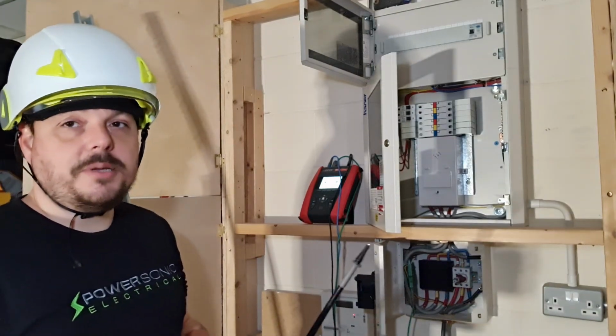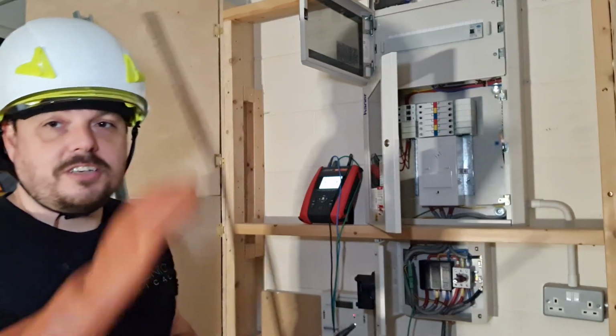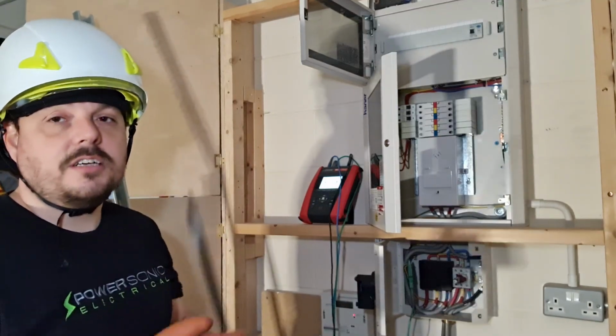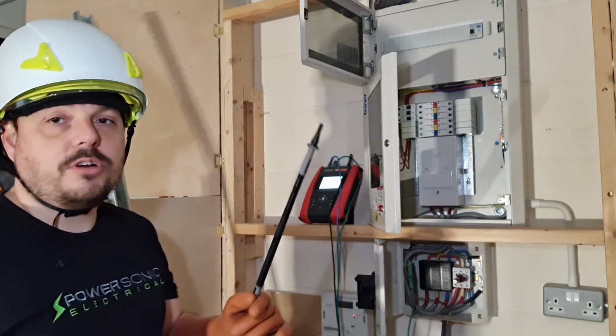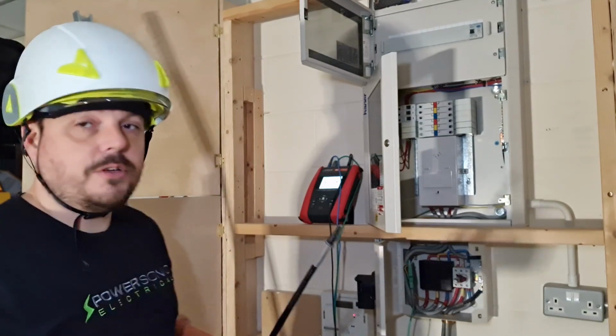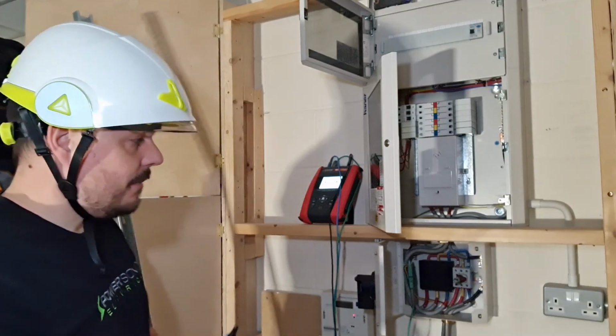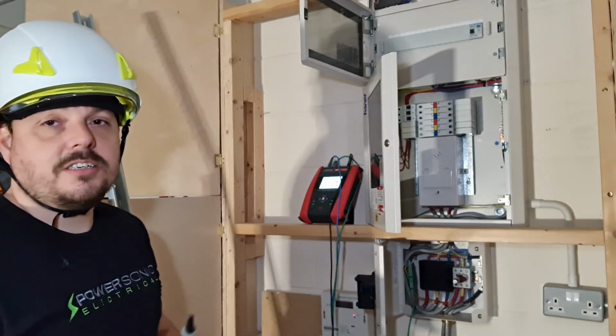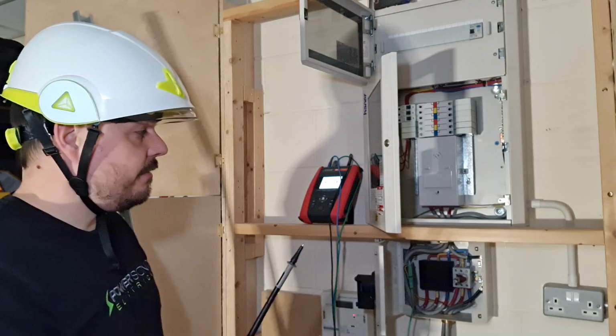You'll see I'm in a bit of PPE, so I've got my helmet and face shield on, got some rubber gloves on. It is a live test, also utilising an extended probe. You can wear an arc suit if you wish. We do have them.